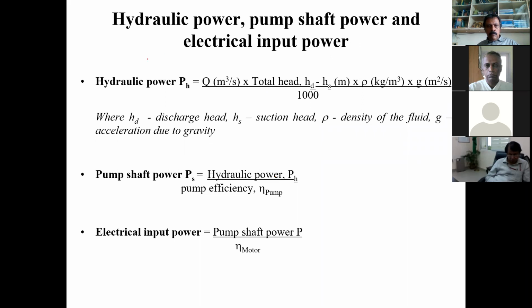So the hydraulic power, that is, if you have an electric motor, then you have a pump, and the pump is delivering some water here, output. So what is the power in the water? This is called the hydraulic power. So it is mgh. Q is the flow, H is the total head, which is discharge head minus suction head, into the density into the gravitational constant, divided by 1000. This is the hydraulic power, this is power in the water. To deliver this much hydraulic power, what should be the input power?